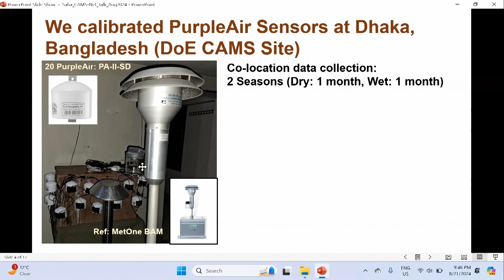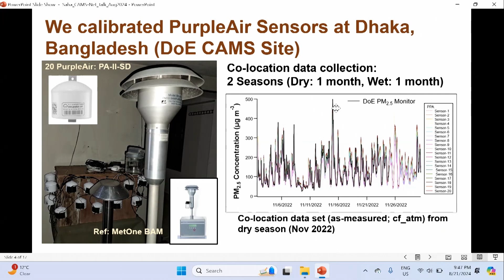This trace shows one example of the collocation data. The black trace shows the data from this BAM, the DOE PM2.5 monitor, and the different colored traces show the data from individual sensors. These are the sensor data as measured with CF-ATM. The sensors report PM2.5 using two different internal calibration factors, one is CF-ATM and the other is CF1. This is with the CF-ATM. You see there is excellent consistency in the measurements from different sensors, and as measured with CF-ATM it is kind of aligned with the BAM data.